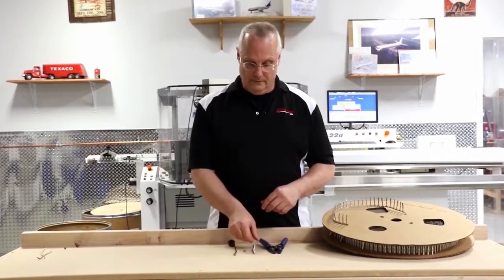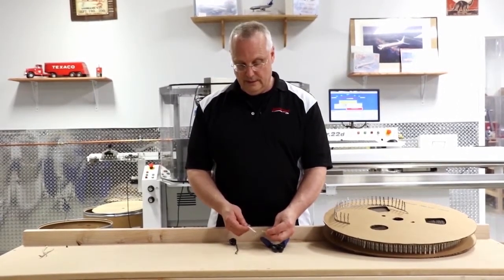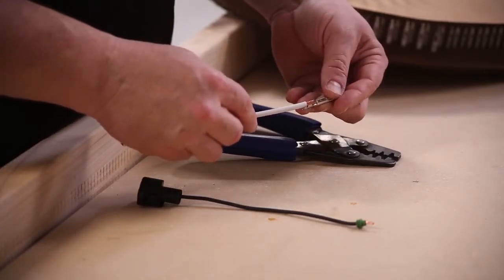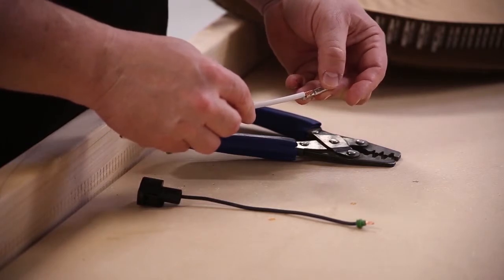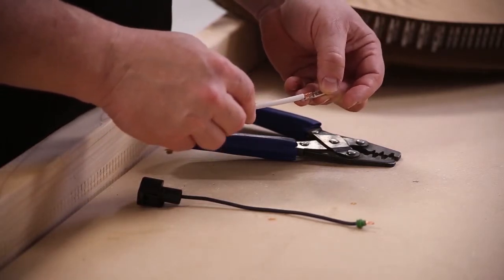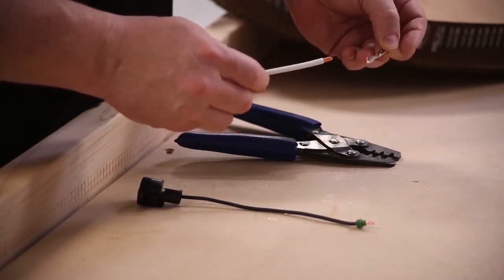Let me give you an example. We have a terminal here, and this terminal and wire gauge are not made correctly, and you can see it's too big for this terminal. But there have been people who have put this wire onto that terminal. Maybe they solder it because they don't know they can acquire a terminal to fit the correct wire gauge.